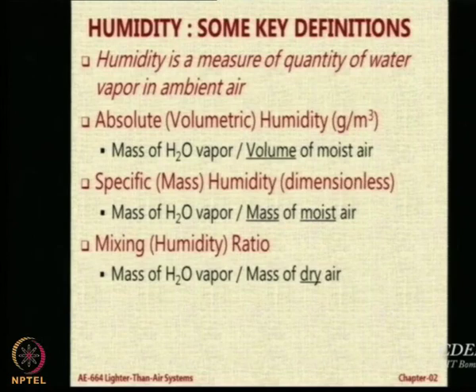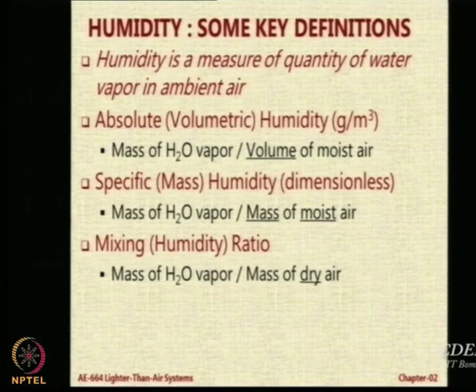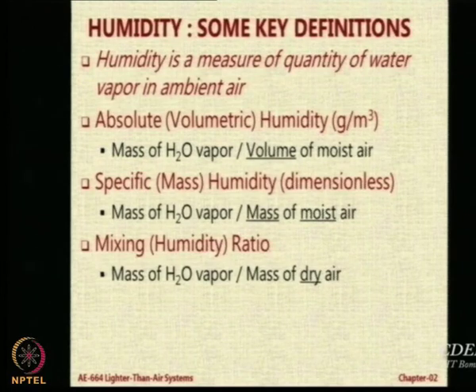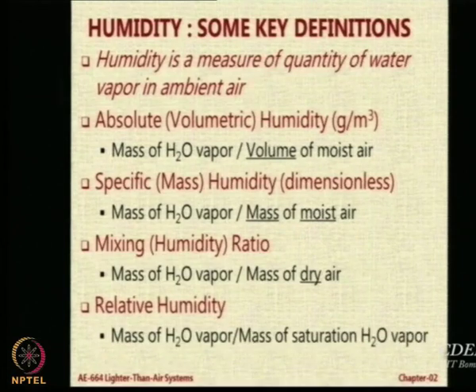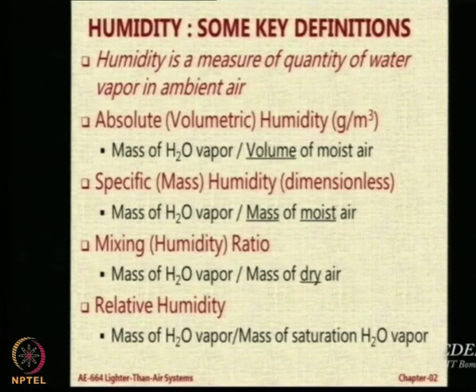Then you also have what is called a humidity ratio or mixing ratio, which is the ratio of mass of water vapor upon mass of dry air. So you remove the mass of the water vapor and the remaining thing is mass of dry air. That ratio is called the humidity ratio. Most important for us is what is called RH, or relative humidity, which is mass of water vapor divided by mass of the saturation water vapor.